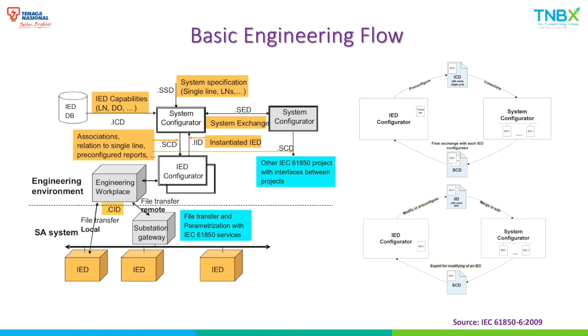In the revised version of Part 6, commonly known as Part 6 Edition 2.1, the standard already acknowledges the mixture of editions in the engineering process. It highlights that an edition 1 IED can only work with a tool that supports both edition 1 and edition 2, whereas a tool supporting both editions can always work with edition 2 devices. This means there's no direct engineering process that can support bringing edition 1 into edition 2 configurations as far as SCL is concerned.